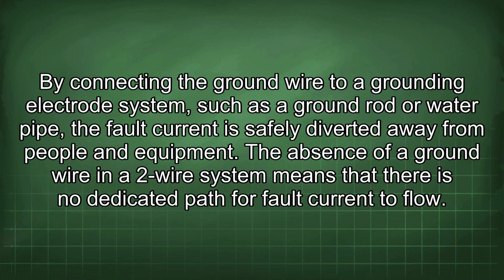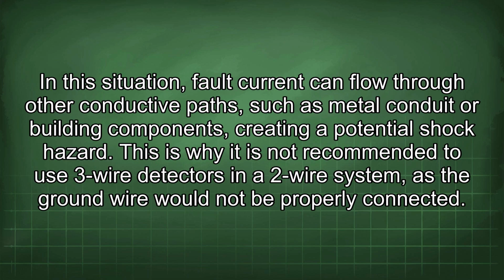By connecting the ground wire to a grounding electrode system, such as a ground rod or water pipe, the fault current is safely diverted away from people and equipment. The absence of a ground wire in a two-wire system means that there is no dedicated path for fault current to flow. In this situation, fault current can flow through other conductive paths, such as metal conduit or building components, creating a potential shock hazard.